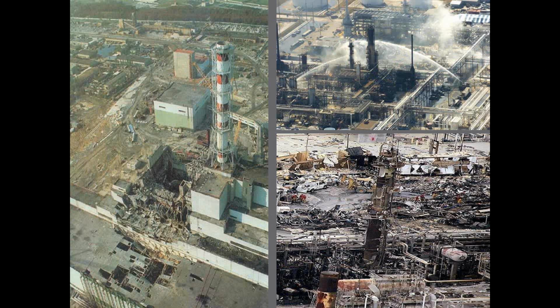The reactor eventually overflowed to the flash pot you see on the right-hand side, the little skinny stack. The level transmitter in the skinny stack didn't work to light the flare. And there was a high-level switch in the reactor itself that didn't react. So 3 electronic devices failed that day. And due to that reaction, there were 15 people killed, 12 contractors and 3 operators. So again, failure finding task.